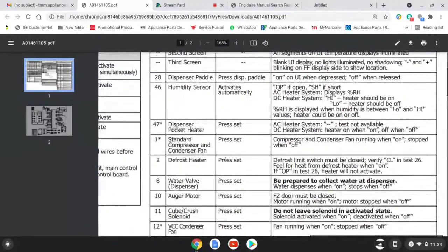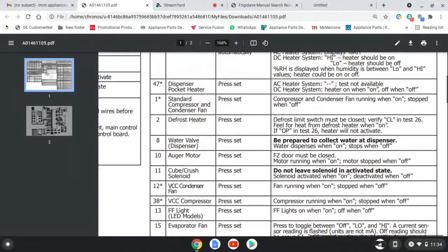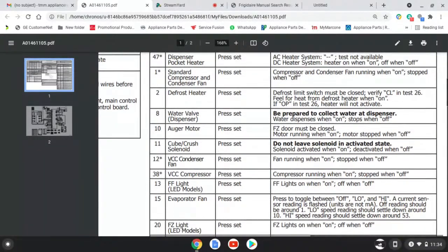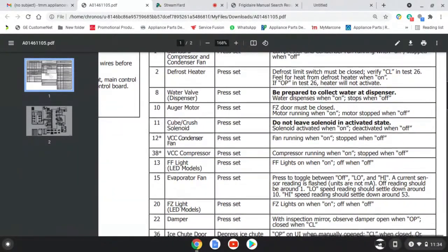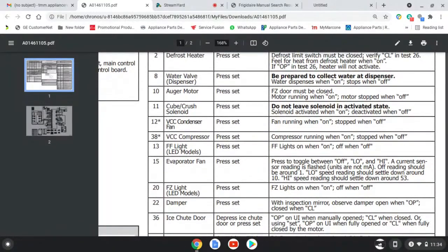Defrost heater - you get to a unit that's all frosted up in the back by the evaporator, and you're in question whether it's the board, the bimetal, or the defrost heater. Well, you can put the unit in diagnostic mode and activate that defrost heater. You can also use your water valve, your auger motor, your solenoid, your condenser fan, your compressor - I guess you can even isolate them.